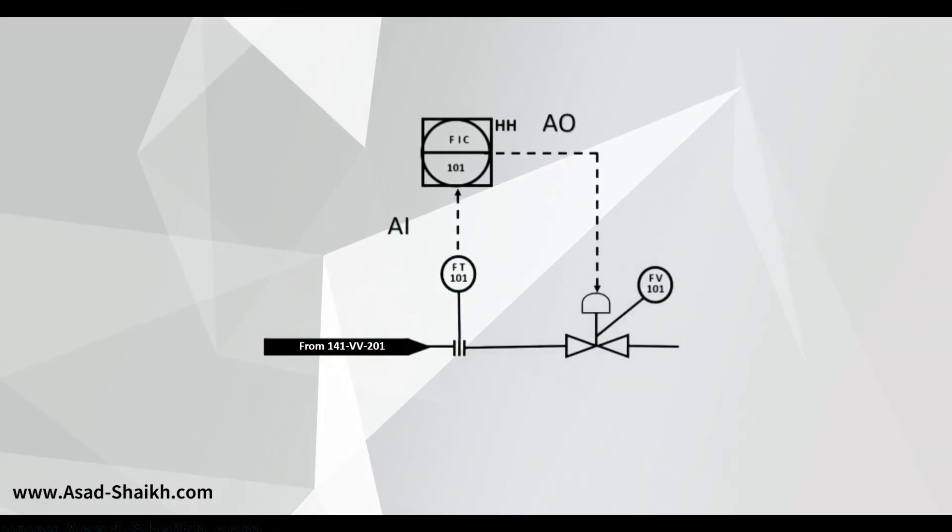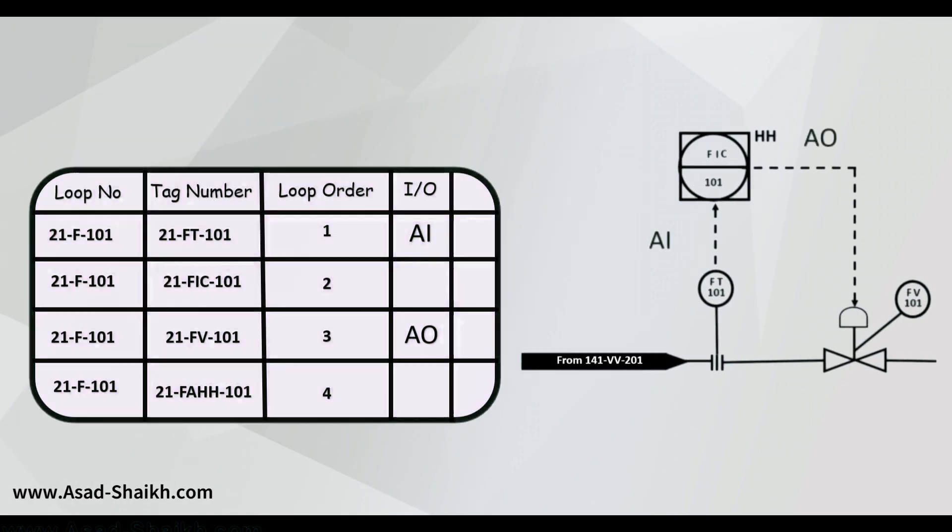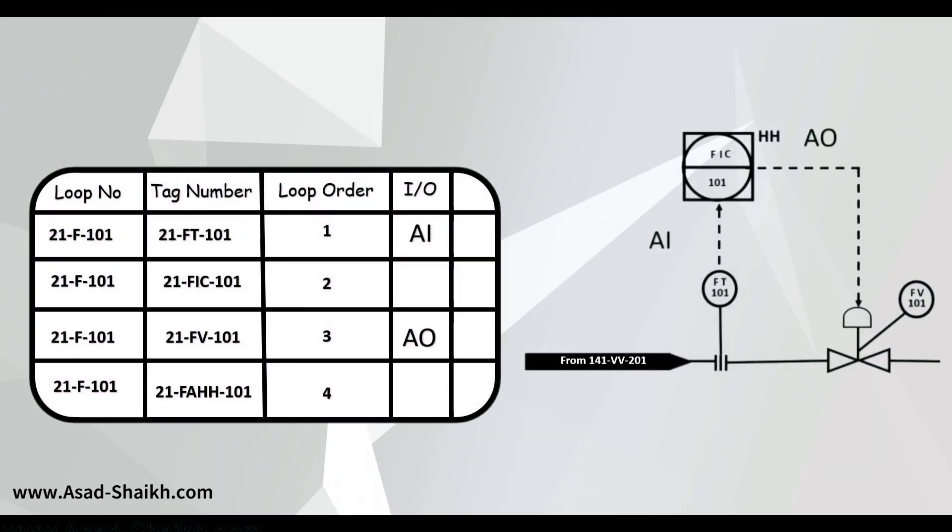We are already clear that the transmitter will give an analog signal which is generally 4 to 20 milliampere which goes to your control system. From a control system an analog signal of 4 to 20 milliampere will go to your control valve. Now we document these I/Os into the instrument index.